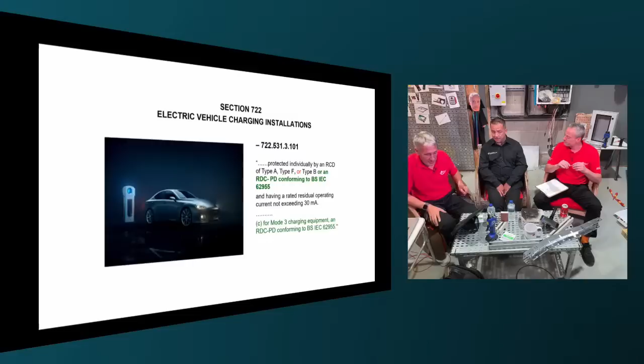Yes, and if you remember, as it is now in the Brown Book, it says you can have the charger with the RCD internal or external, but it has to conform to one of the RCD standards, 61008 or 61009. Whereas these electronic RCDs don't.